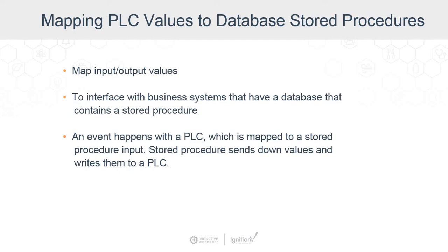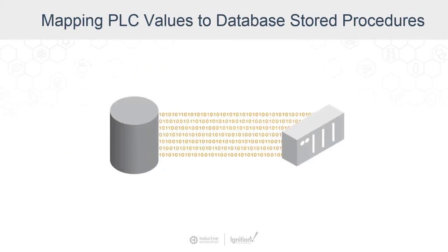When a PLC event or trigger happens, we can run a transaction group that sends values to a stored procedure in the database. The procedure executes and the results are sent back to the PLC, effectively handshaking the PLC with the database. This is a very commonly used pattern for many applications. It also keeps more logic in the database, keeping Ignition cleaner without requiring scripting. In fact, transaction groups largely eliminate the need to do scripting in Ignition.